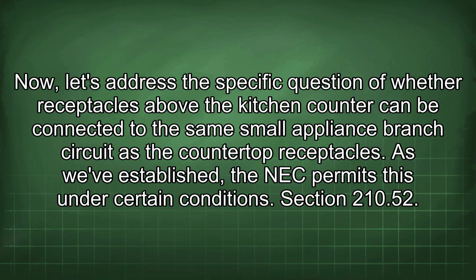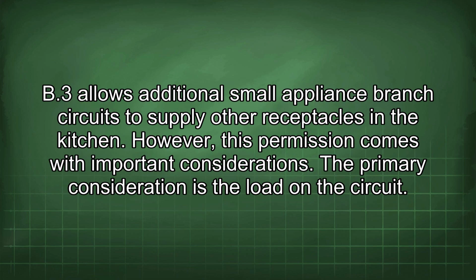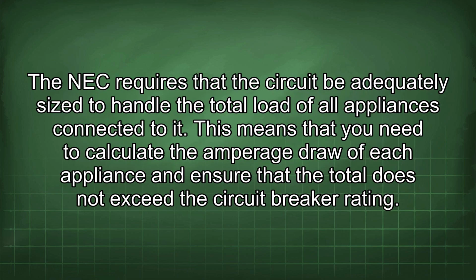As we've established, the NEC permits this under certain conditions. Section 210.52(B)(3) allows additional small appliance branch circuits to supply other receptacles in the kitchen. However, this permission comes with important considerations. The primary consideration is the load on the circuit. The NEC requires that the circuit be adequately sized to handle the total load of all appliances connected to it. This means that you need to calculate the amperage draw of each appliance and ensure that the total does not exceed the circuit breaker rating.